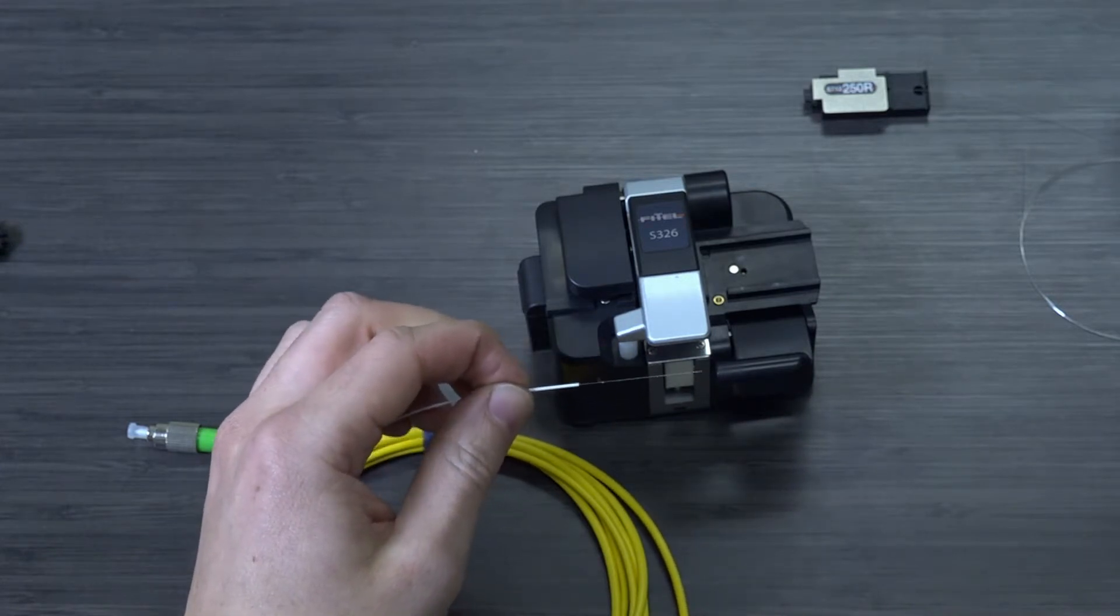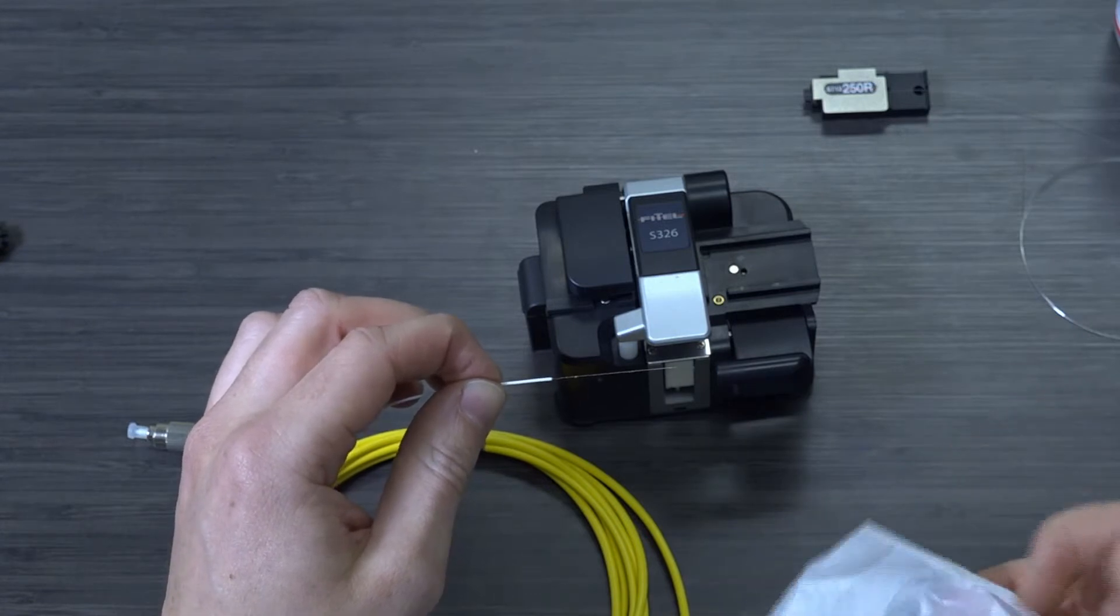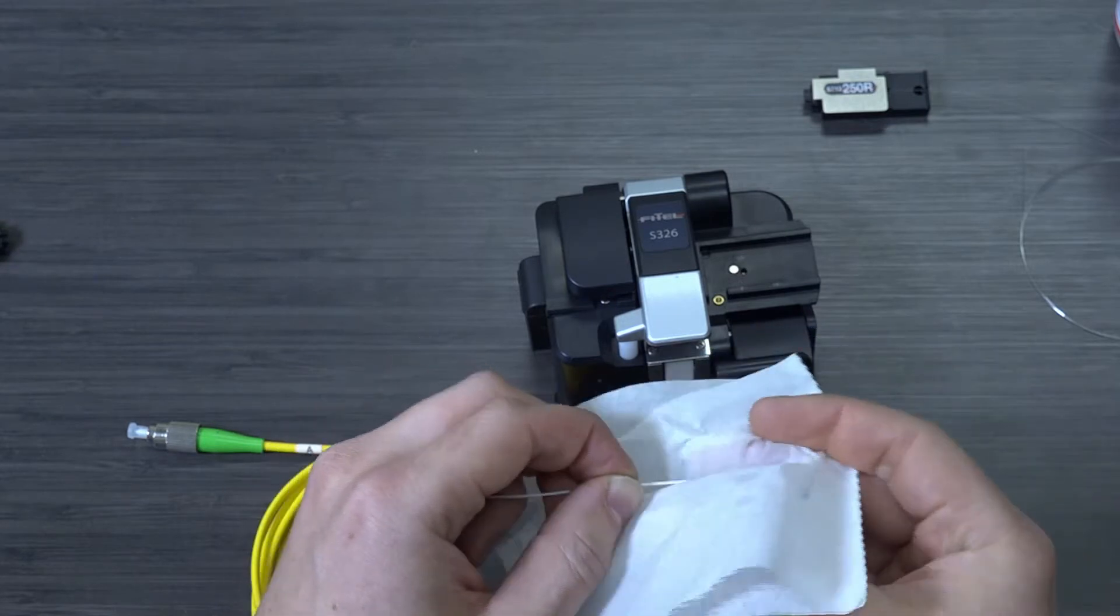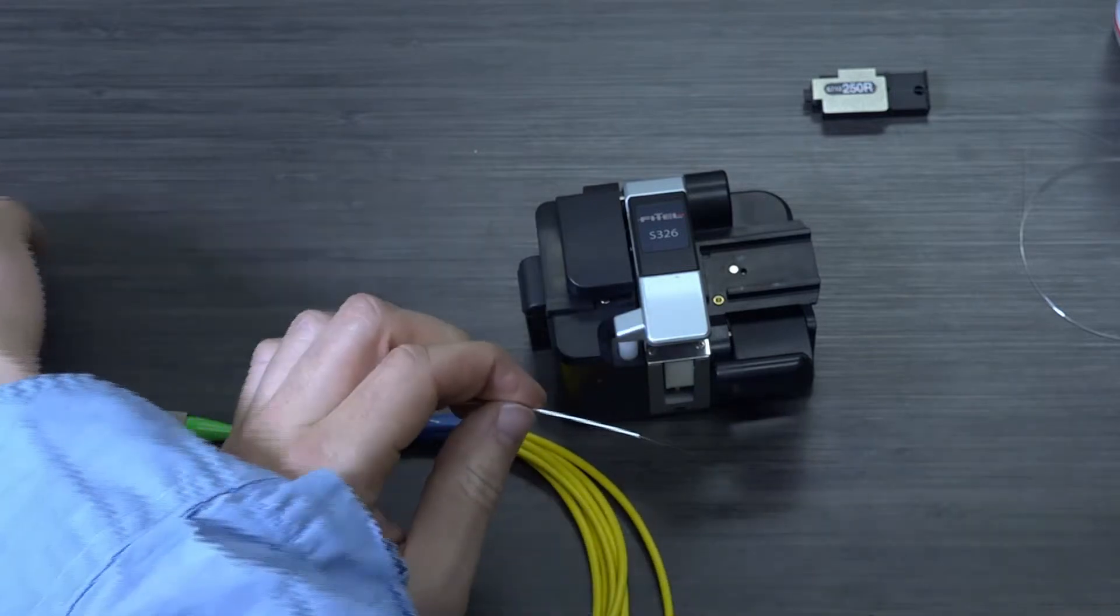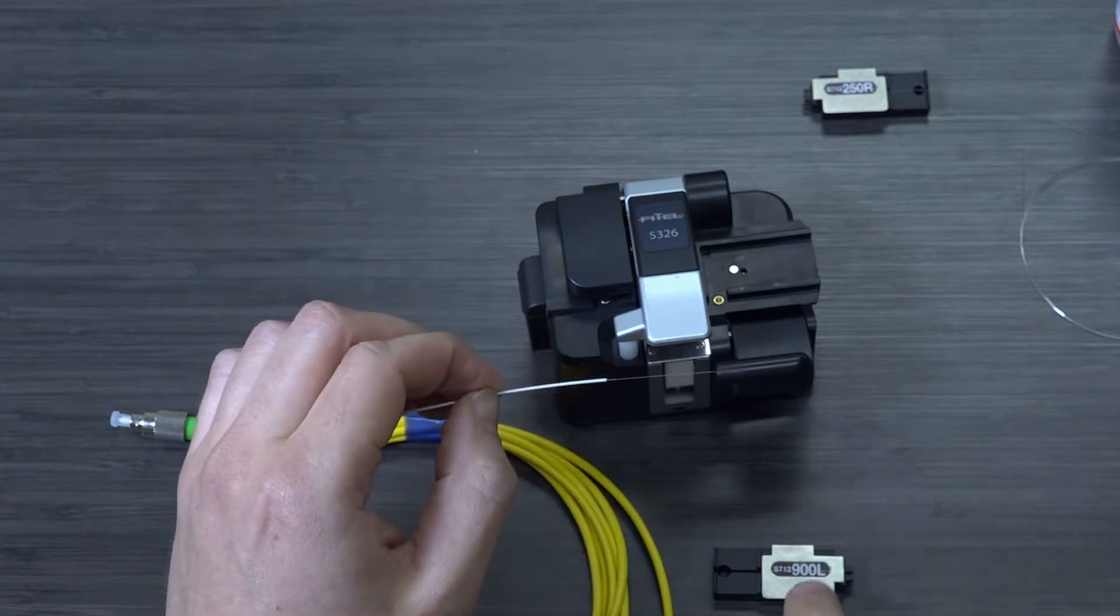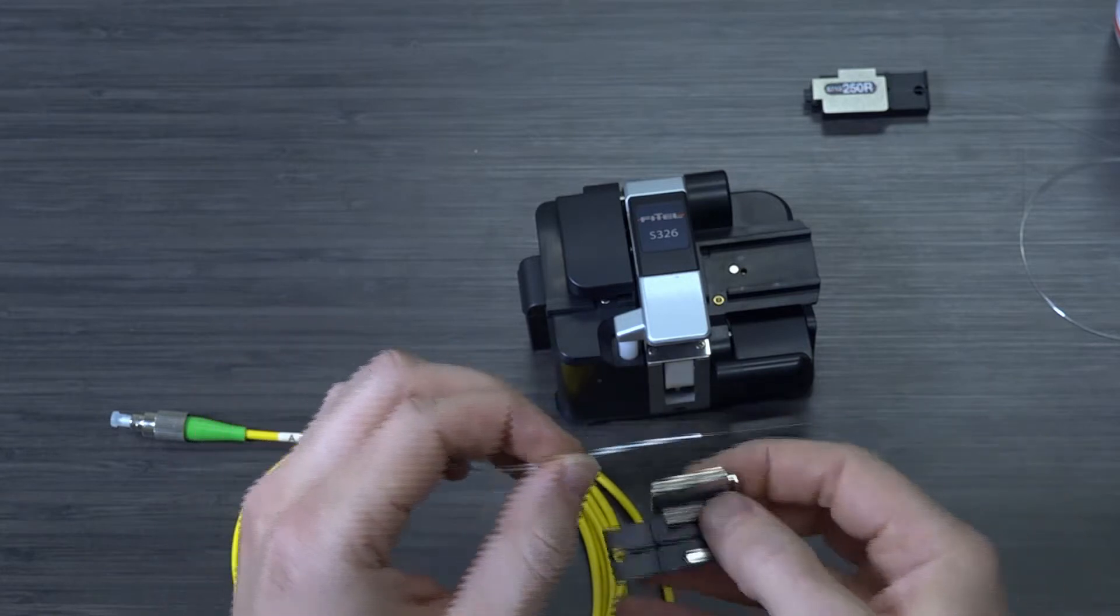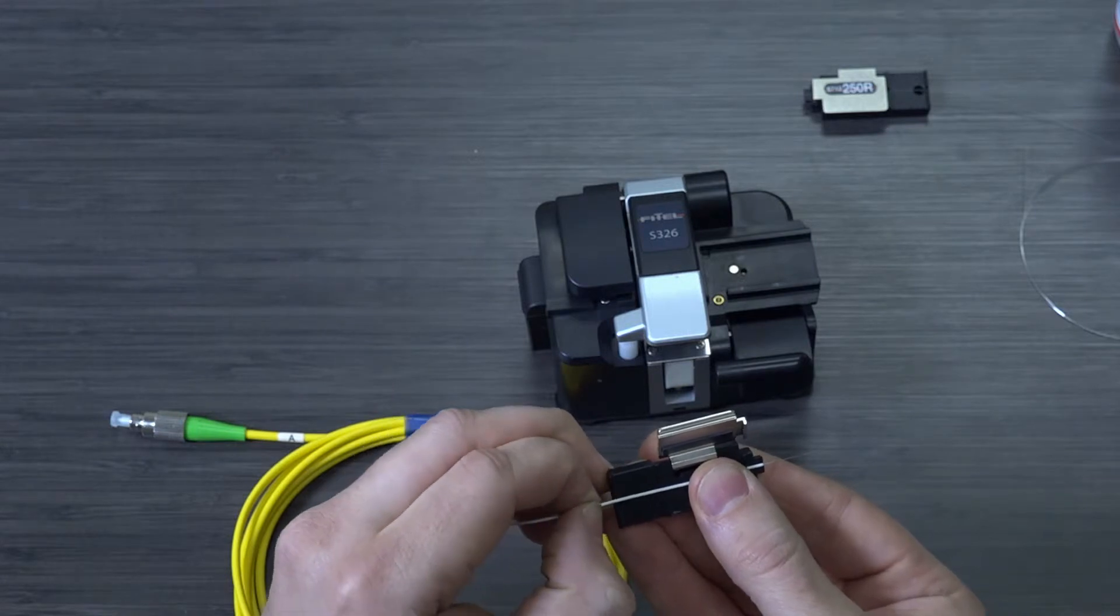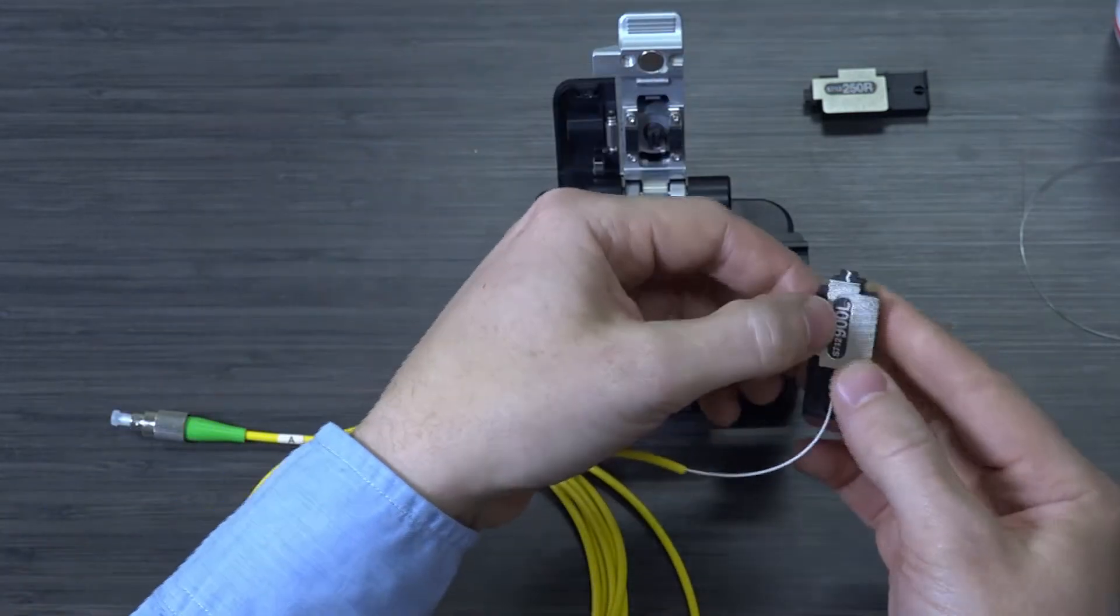Just like the previous fiber, the next step is to clean. So I'm going to use a little bit of isopropyl alcohol and a lint-free wipe. And then again we use our fiber holders. However in this case because we're going to be holding on to this part of the fiber, which is 900 microns, we are using the 900L fiber holders. And from here on out it is the same procedure as previously performed.